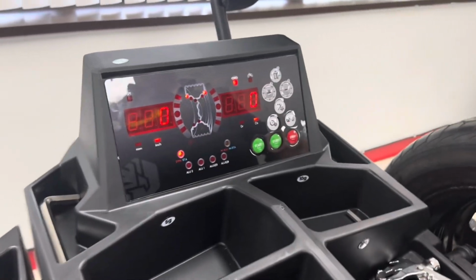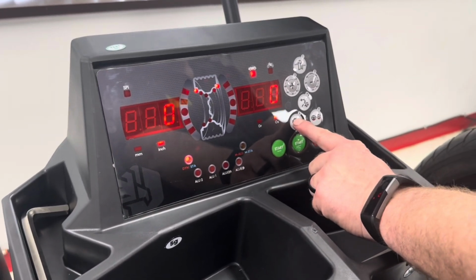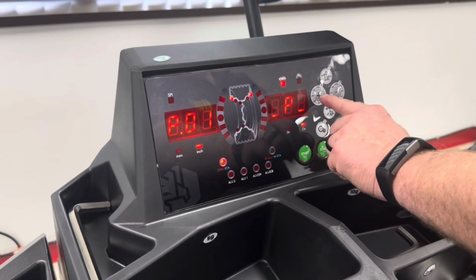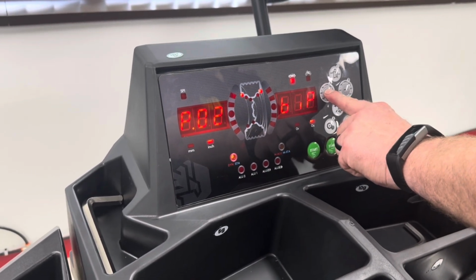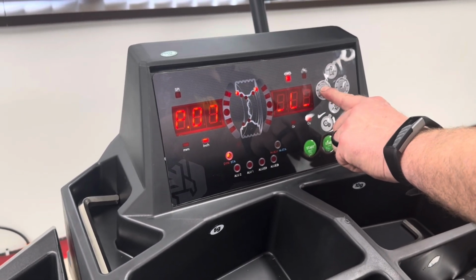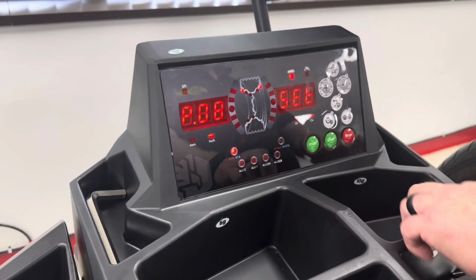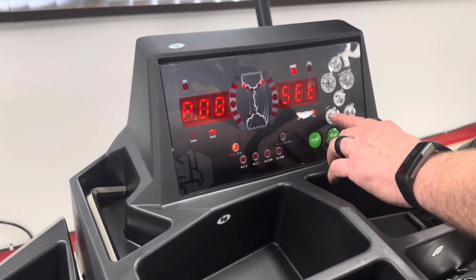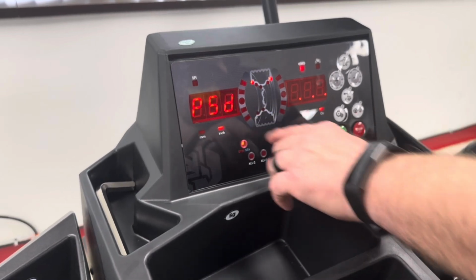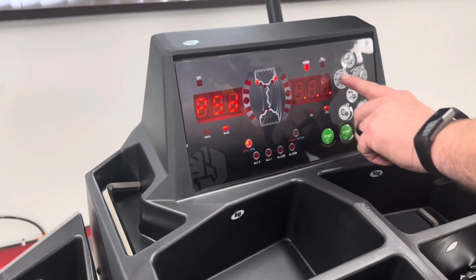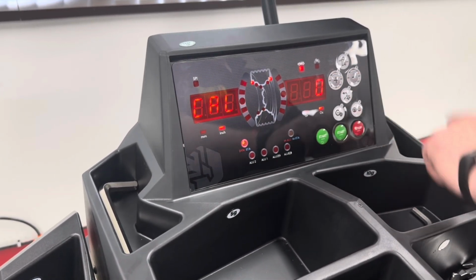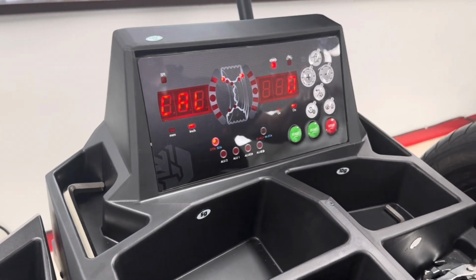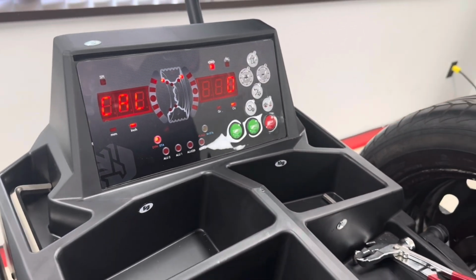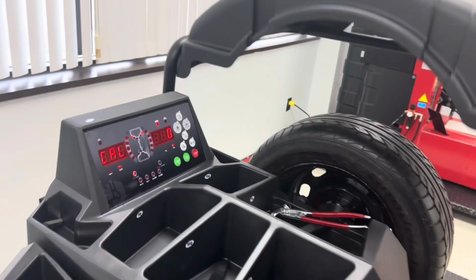We'll go to our machine and use button number 5 to select the programming, then hit plus until we get to number 8, our setup. We choose 5 to enter that. It brings up our password, which is plus, plus, minus, and it puts it into Cal 0. Once it's in this position, you simply close the hood.